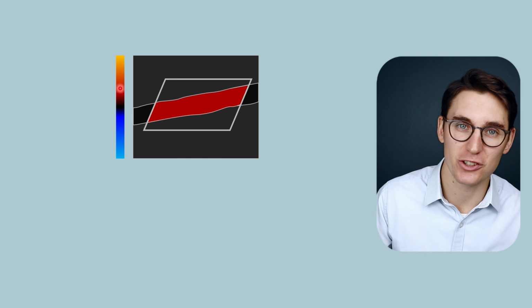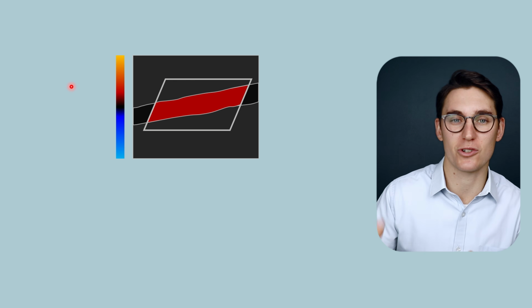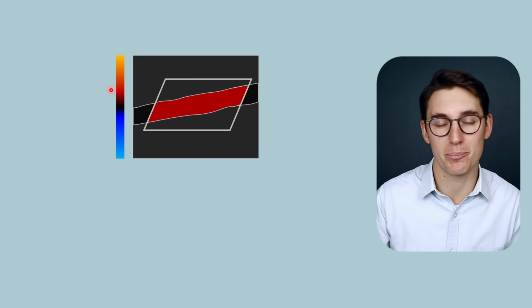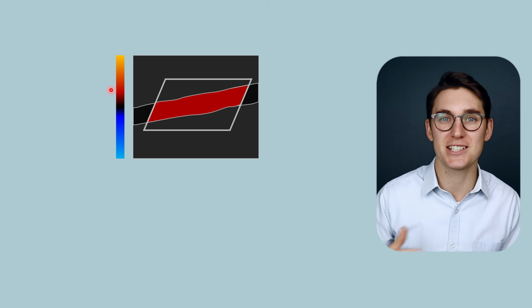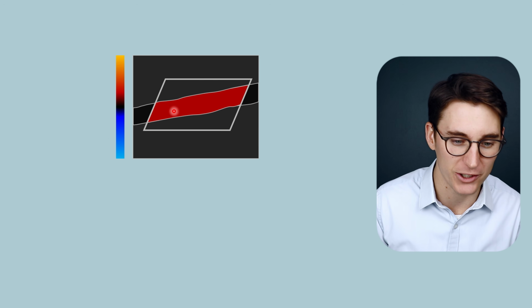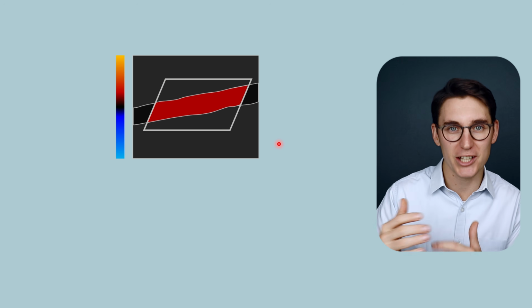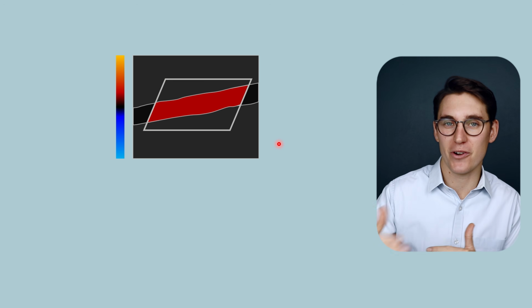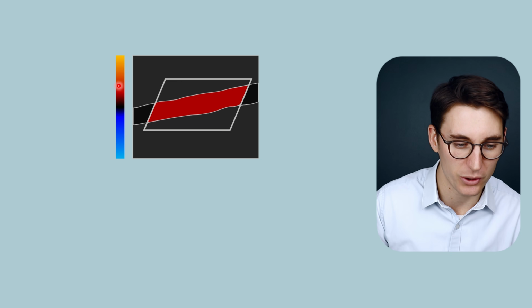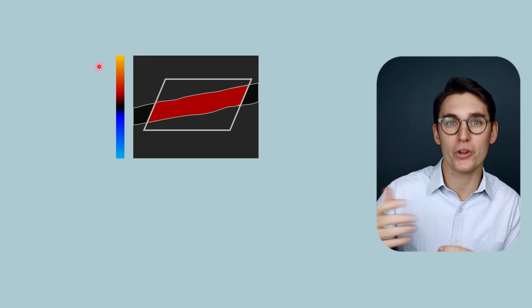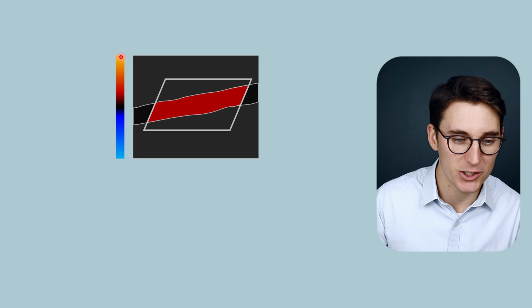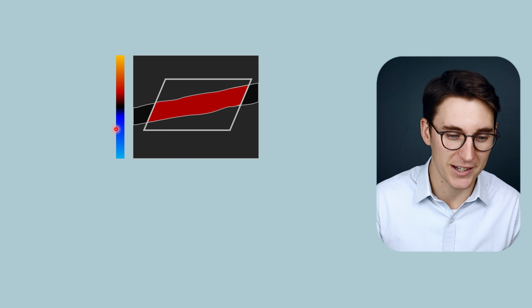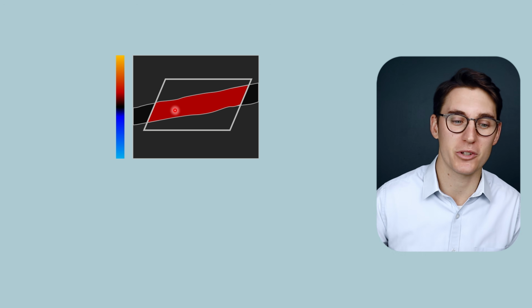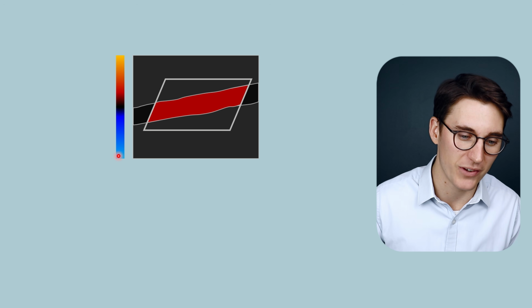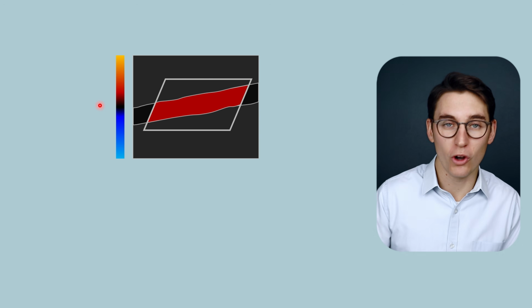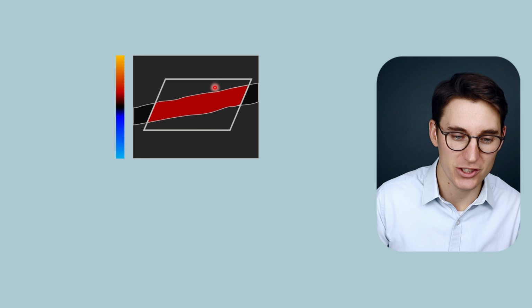So we're getting a directional value here. If blood's flowing towards our transducer, we get values in the red scale. If blood's flowing away from our transducer, we get a negative Doppler shift value. We assign blue values in this active area. So there's a directional component here. Not only is there a directional component, there's a magnitude component. The higher the velocity, the more the Doppler shift, the brighter these colors will be, closer to orange than they are to red. And in the blue regions, the higher the velocity away from the transducer, the more light the blue values get. If there's no movement, no velocity, then we get black in the regions of this active area here.